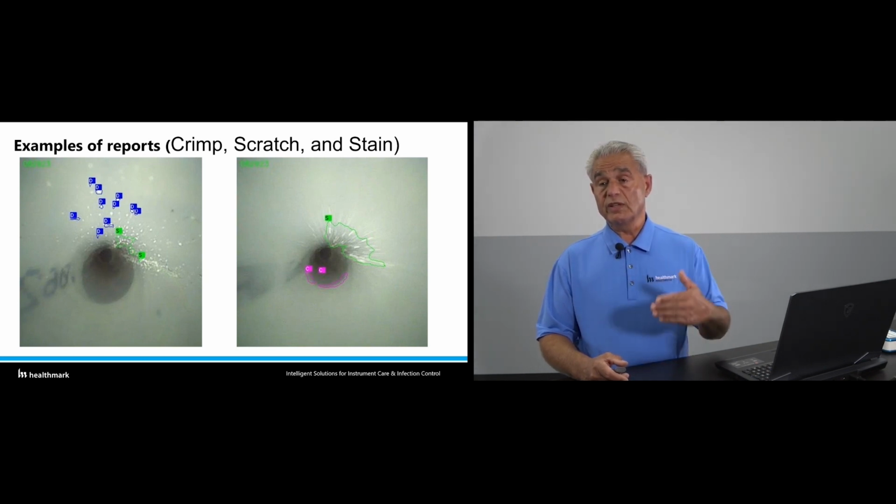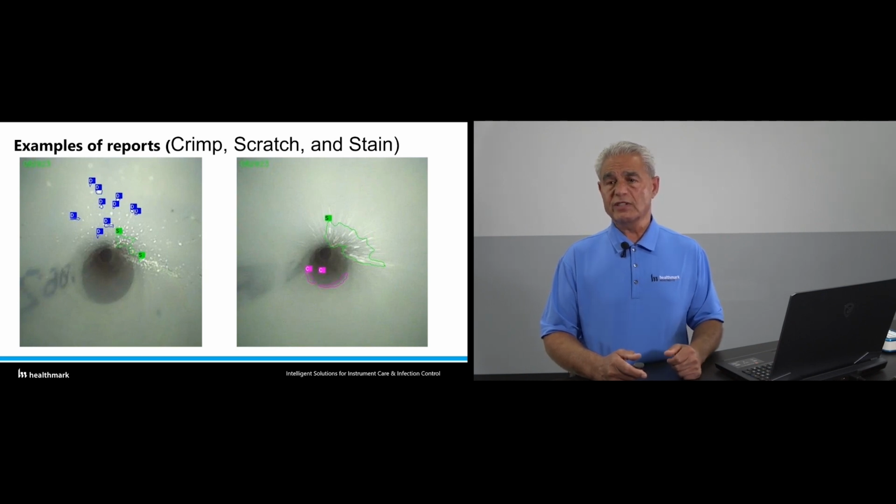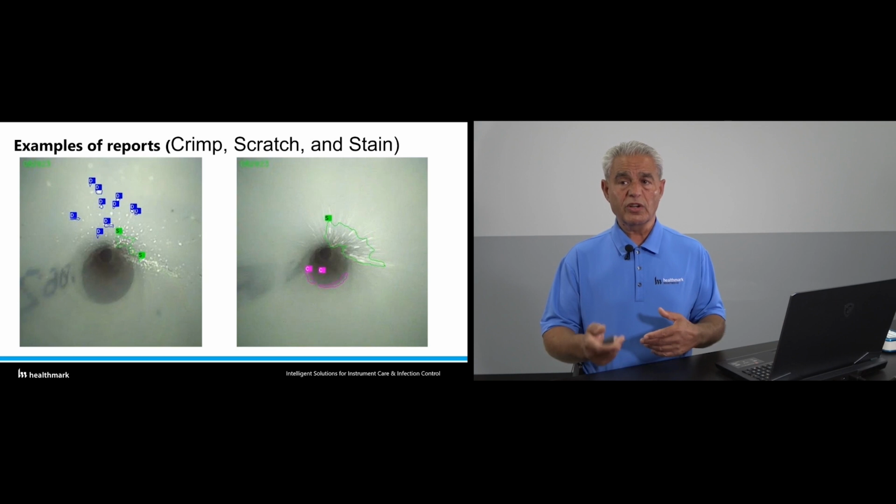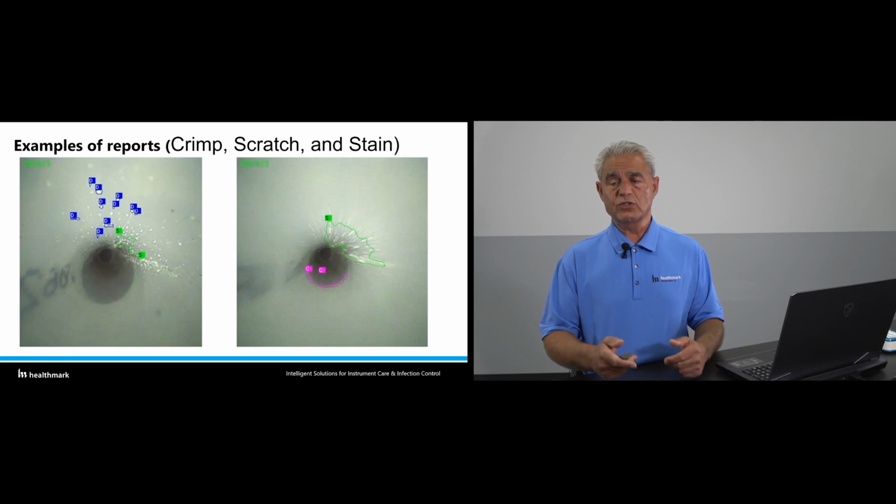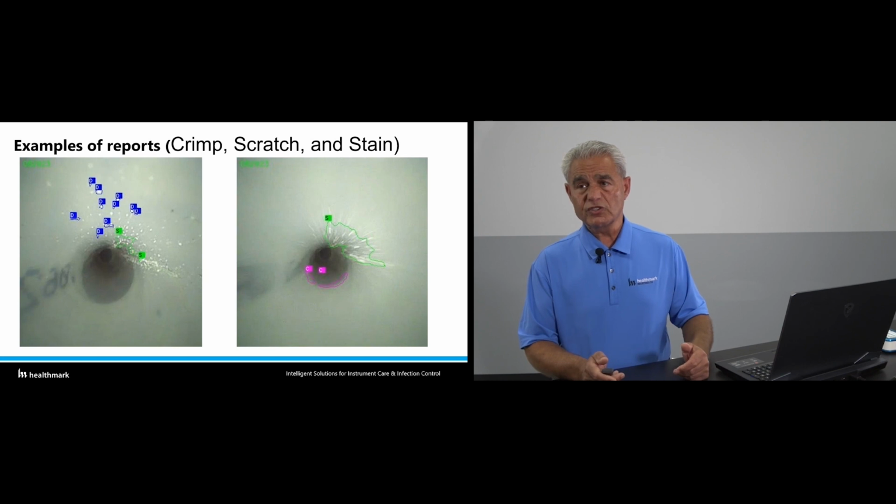The cannulated. Once we identify that those are the issues, we can actually teach the AI not to count those as deficiency. We were approached by another endoscope manufacturer that in their process uses some adhesive that is brownish or tan in color. So once AI identifies those, it can not count those, and look at those as part of the normal process of the endoscope. And if there's a scratch or debris on top of that, it could count those. So that's the advantage of artificial intelligence.